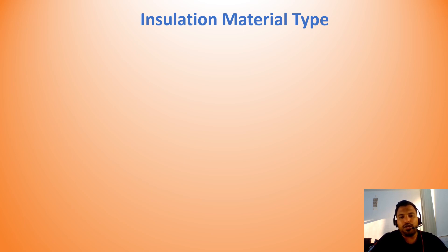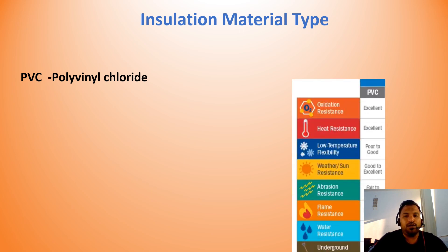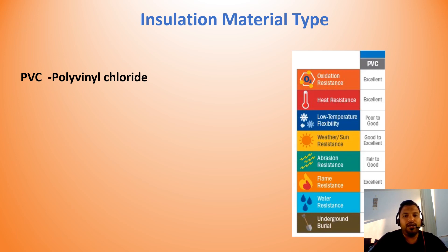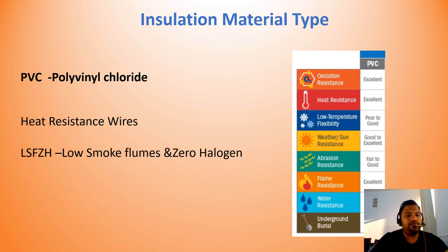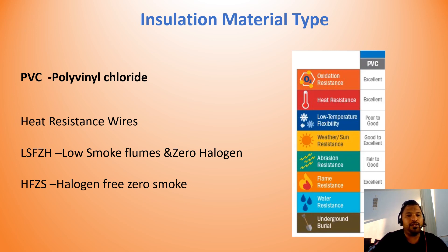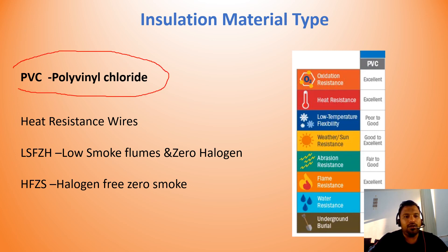The second element while selecting wires is insulation material. The material should be PVC — polyvinyl chloride — which has good properties like high oxidation resistance, excellent heat resistance, and excellent flame resistance. In the market, you will also see heat resistance wires, LSF-ZH (low smoke fumes and zero halogen), and HFZS (halogen free, zero smoke). These are all PVC-based wires with enhanced properties.